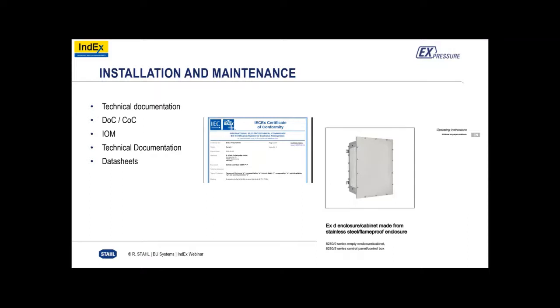Follow what the certificate says, the manufacturer's installation, operation, and maintenance manuals. So that means the technical documentation, the data sheets, the installation requirements. So this is a certified piece of kit for IECEx and ATEX. All that must be followed is clearly defined. Remember, you don't do as the standards tell you. You do first what the certificate tells you, then the manufacturer tells you, then the standards.